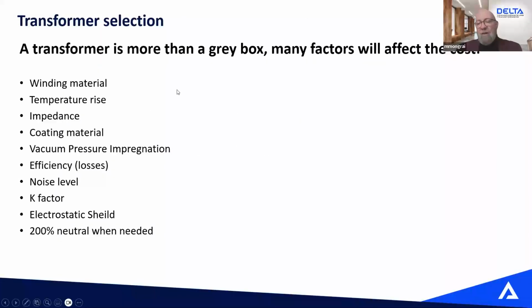So when you select a transformer for any type of application, make sure that you analyze your needs, the requirement, and then what winding material will I go with? Copper, aluminum, what temperature rise transformer do I need? What's the impedance I need? Do I need a specific coating material such as epoxy or something else? Does it have to be vacuum pressure impregnated? Most of the time, we strongly recommend to have at least a VPI transformer, and preferably with epoxy.